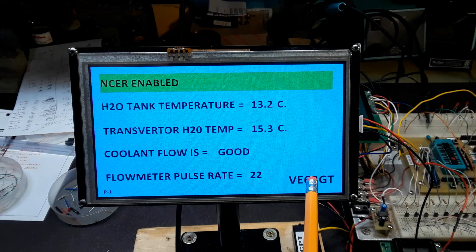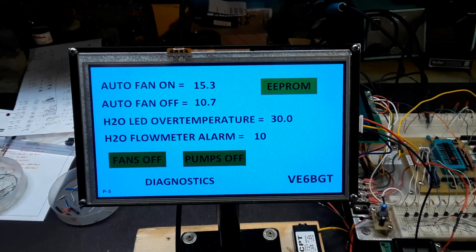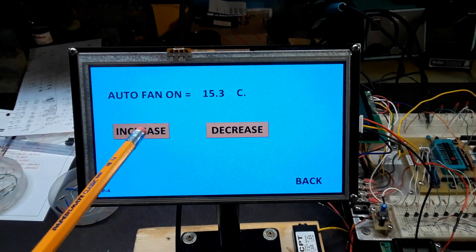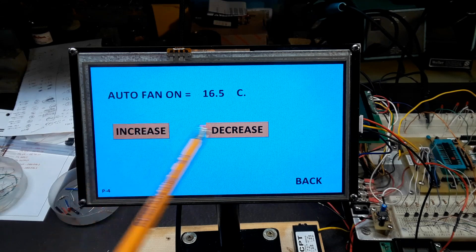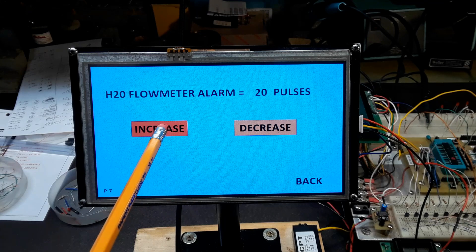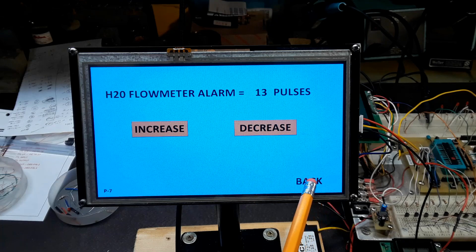This next screen is showing the individual tube temperatures, which again are fixed numbers in the PIC circuit for testing. The third page of the display is where all the set points are set and are adjustable, plus the buttons for turning fans and pumps on and off. This adjustable set point is the temperature point where the cooling fan on the radiators will come on. This one is showing the set point for the flow meter alarm to be triggered. All these set points are adjustable — going up and down — and save to EEPROM.